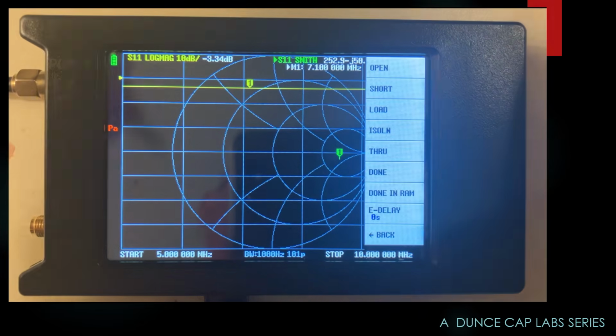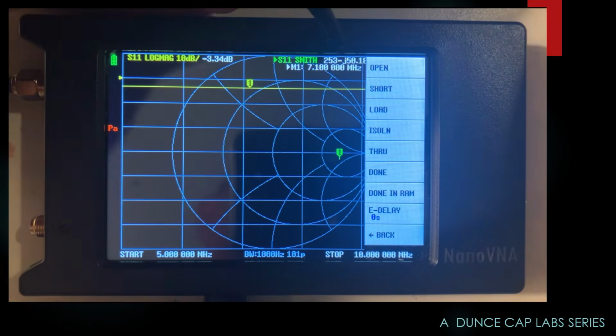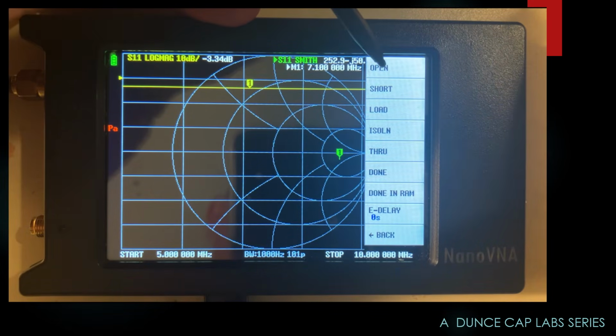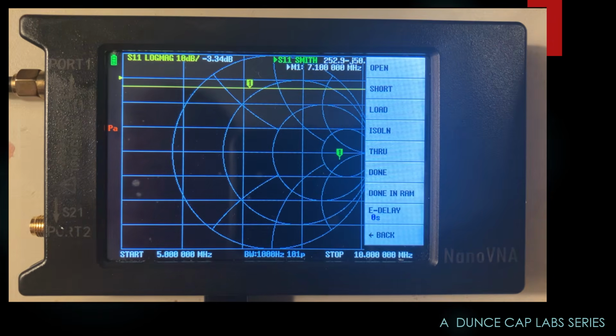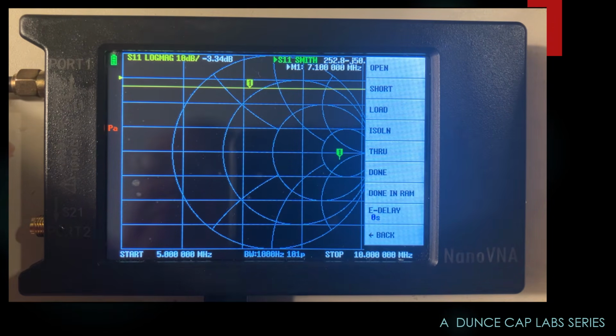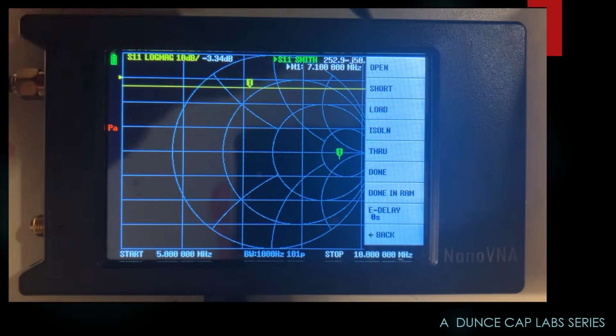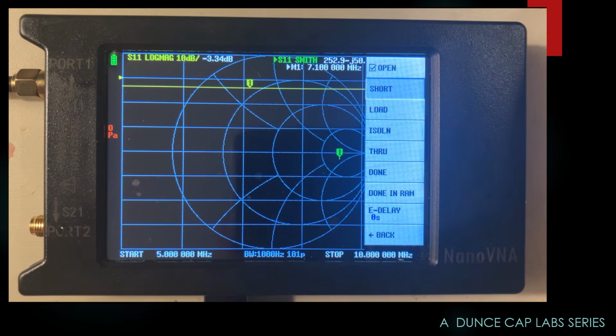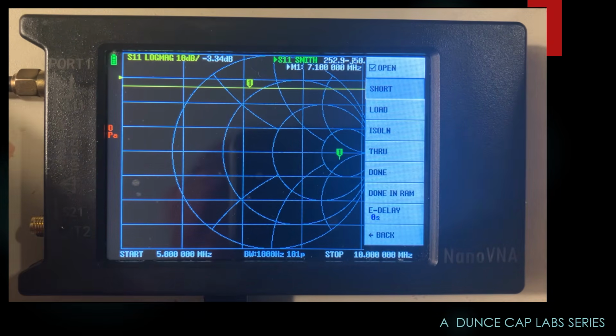Now hit calibrate. The menu is going to guide you in what to do. It wants an open first. So take your little open adapter or termination, tighten it onto the end of the cable, hit open. Wait for the checkbox. Okay, now it wants a short. Take off your open, put the short on.